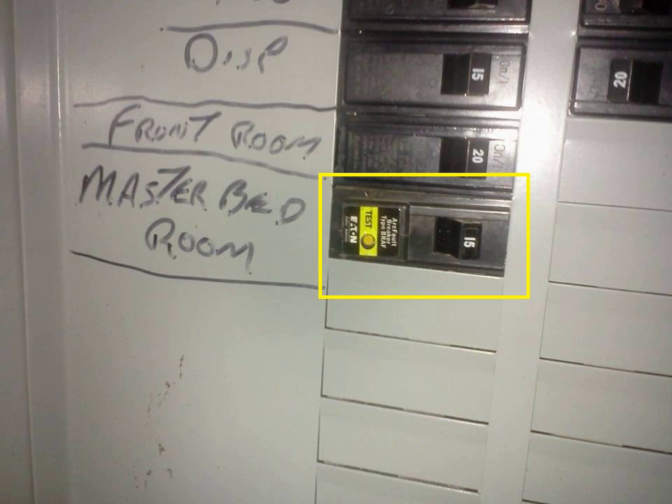This requirement may be accomplished by using a combination type breaker — a specific kind of circuit breaker defined by UL 1699 — in the breaker panel that provides combined arc fault and overcurrent protection, or by using an AFCI receptacle for modifications, extensions, as replacement receptacles or in new construction, at the first outlet on the branch.